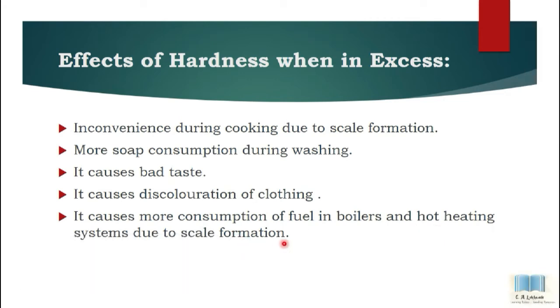Here scale formation means a layer of impurities which is formed on the inside surface of the boiler. Hence heat supply to the water is prevented by the layer of impurities, and hence more heat is required to heat the water inside the boiler, which increases cost as well as energy consumption. So these are the effects of hardness when hardness is in excess quantity.